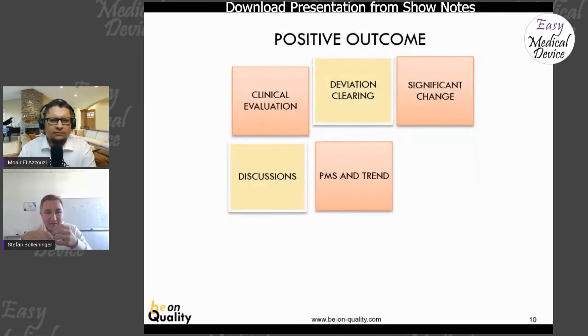We can do internal fixes, we can do internal new structures. We will guarantee to you in your significant change paper that we will not impact the architecture, the risk file, and the intended purpose until that point. And then we will define that it's not a significant change. The notified bodies have been better in discussion than the guidance document itself. So fine for that, and I'm very thankful to the notified bodies as they go that way in many cases, because that will lead us to innovation.